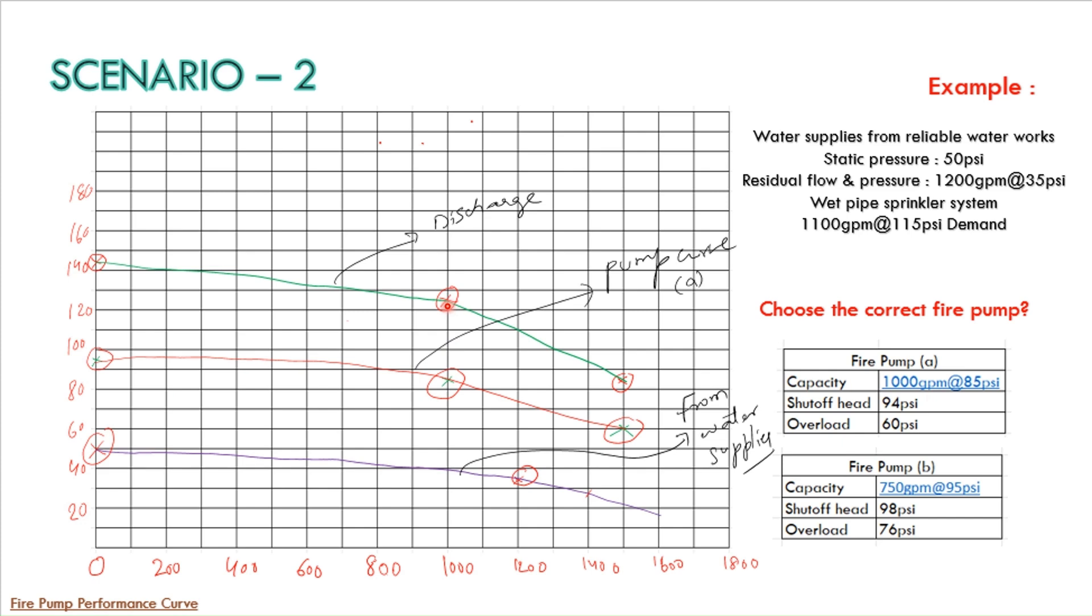Apart from that at 1500 GPM also you can see here you have 20 or 22 PSI plus you need to add this 60 PSI. So it will be around 82 PSI. So we have joined these three points.